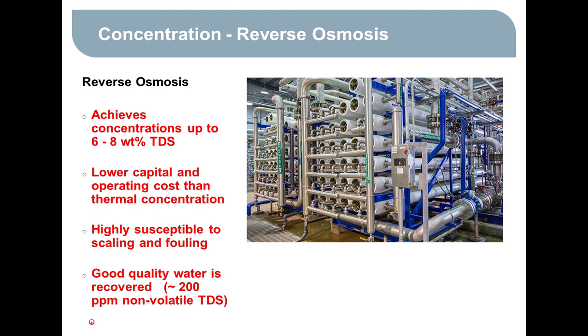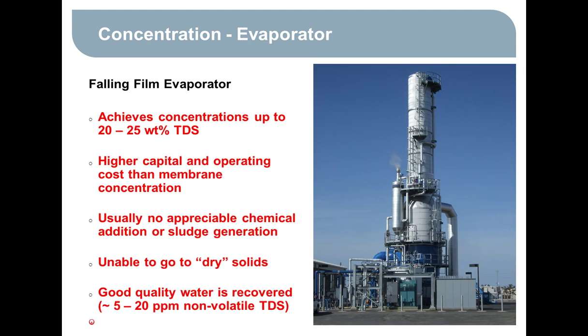As far as evaporators are concerned, they're able to get a much higher concentration level, up to 20 to 25% by weight total dissolved solids. Above that, you're getting into an area where salts start to crystallize out. And unfortunately, a falling film evaporator can't handle the crystallization of solids. It can handle only evaporation. So we have to stay below that 20 to 25% limit of TDS.